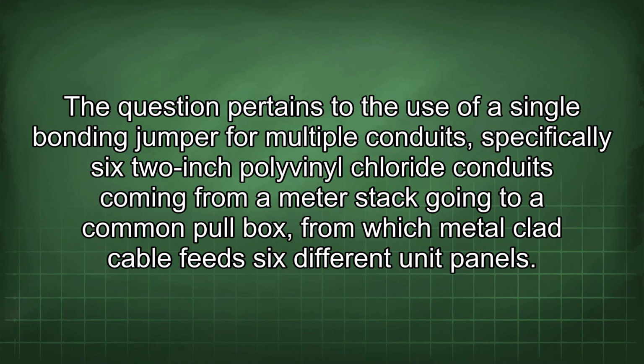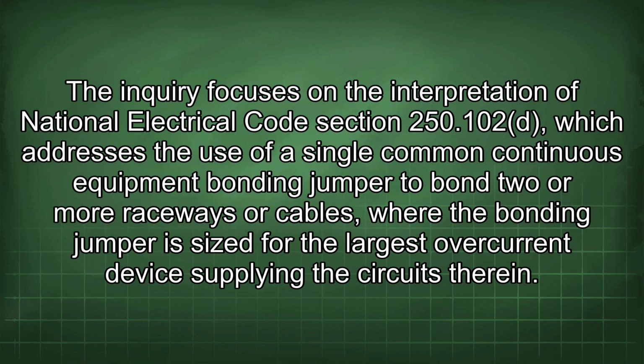The question pertains to the use of a single bonding jumper for multiple conduits, specifically six 2-inch polyvinyl chloride conduits coming from a meter stack going to a common pull box, from which metal-clad cable feeds six different unit panels.